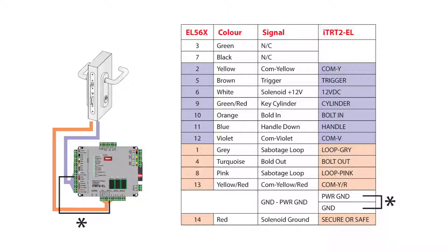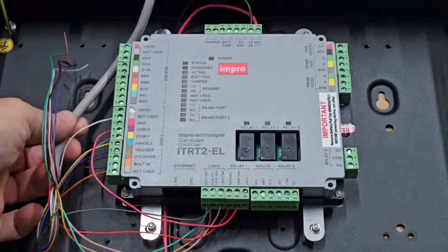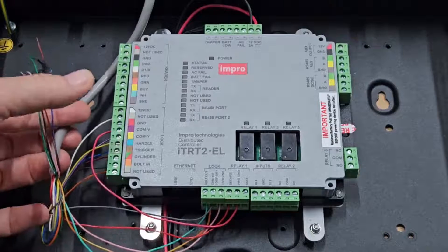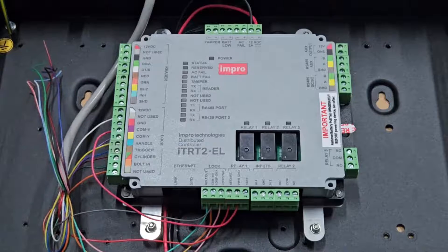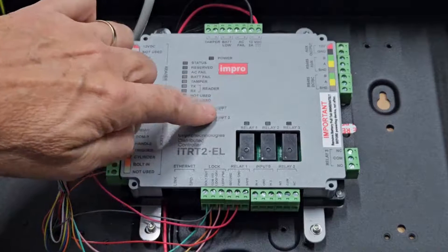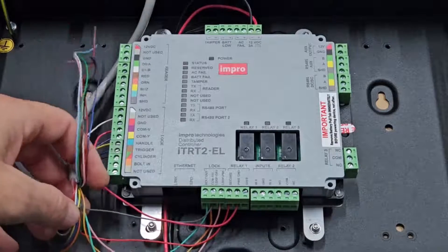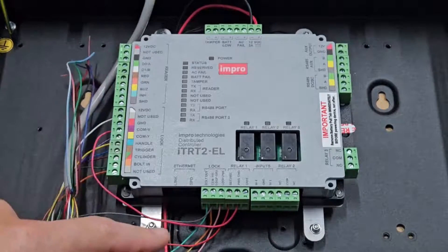You can pause the video between wiring each wire. Begin by trimming off the excess of the EL56X lock cable, leaving it at least 30 centimeters longer than is needed to follow the route from the lock connector to the middle of the controller, and then strip back the outer sheath by 15 centimeters to free up the colored wires.